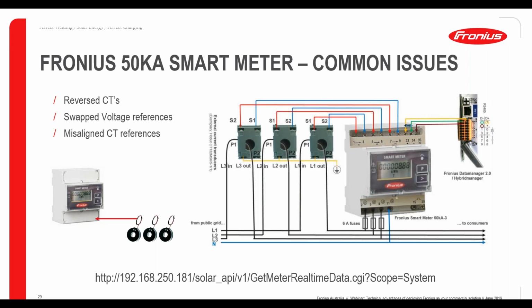As that's being discussed, that needs to be configured in the picture shown here. Also, what I forgot to mention before, I do apologize, this meter comes with an RS-485 capable option that we could use to control systems on site. How this works is the RS-485 is just connected to the plus and minus terminals on the actual data manager on the master inverter, simple as that.